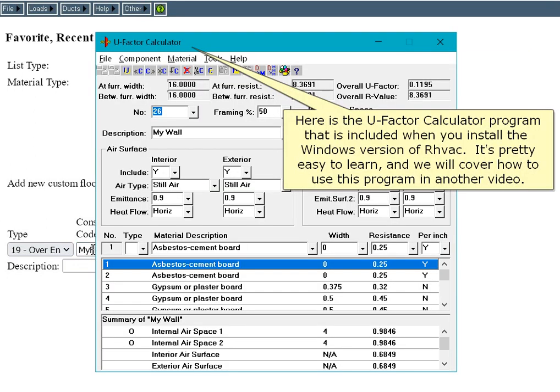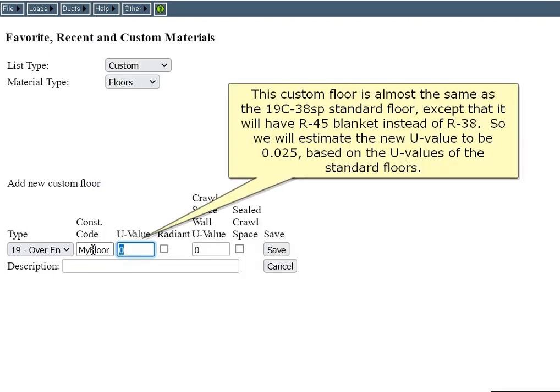Here's the U-factor calculator program that is included when you install the Windows version of RHVAC. It's easy to learn and we will cover it in another video. This custom floor is almost the same as the 19C-38SP standard floor except it will have R45 blanket instead of R38, so we will estimate the new U-value to be 0.025 based on the U-values of the standard floors.